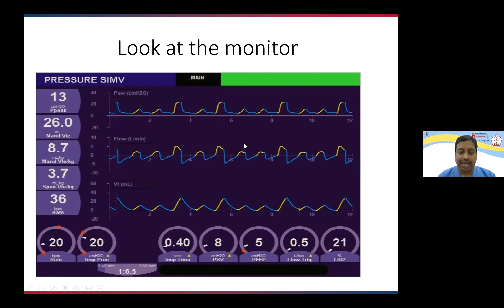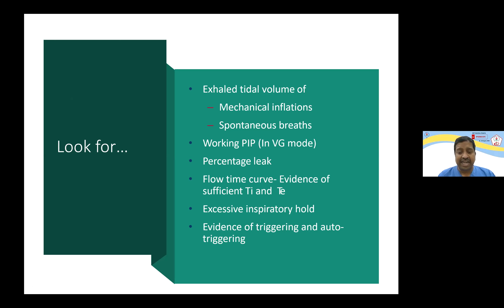Also, a little graphics observation will help you see how the baby is behaving. In the ventilator monitor, you can look at the exhaled tidal volume, compare it with the fixed tidal volume, and see how much the mechanical inflation is translating into tidal volume, and how the spontaneous breath is translating into tidal volume by the baby. You can also check the Working PIP, the percentage of leak, any excessive inspiratory hold, and any problem with triggering, like auto triggering.